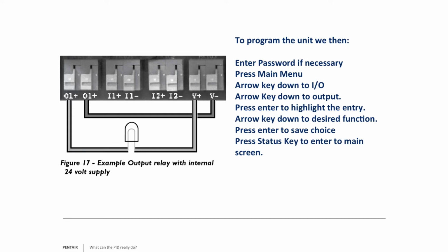And do we want to then decide, is it going to be a run command? So anytime this unit runs, it will close this relay. Or do we want it to be a fault command showing that the unit has stopped running for some reason and it's now sending a signal that there's an issue with our pump or our control? So once you've decided that, hit enter again to save it. And then I, again, always like to hit the status key to take us right out to the main menu. Can you hit the back button to get there? Yes, you can. But I always find it much easier and quicker to hit the status key in the lower left-hand corner of the keypad.